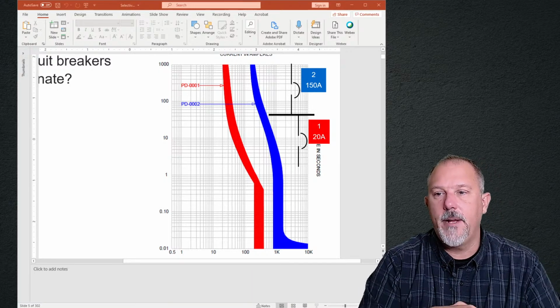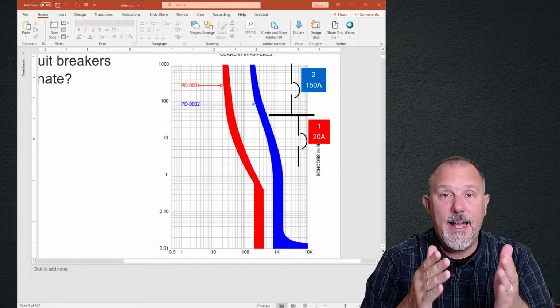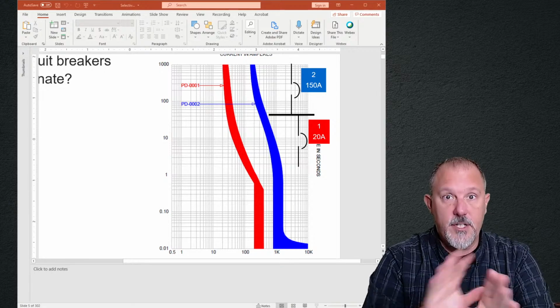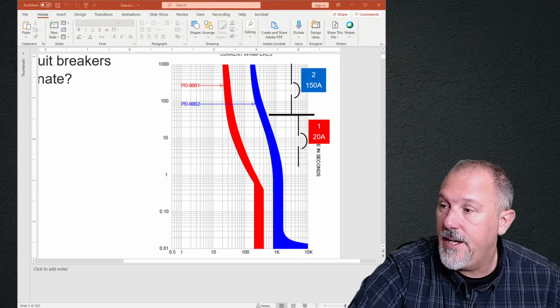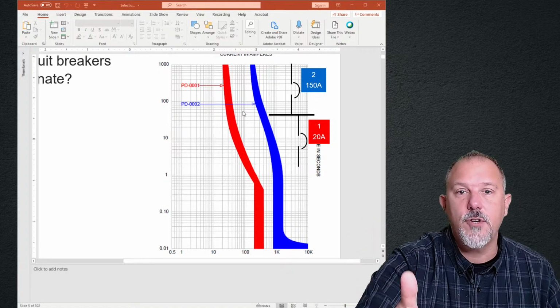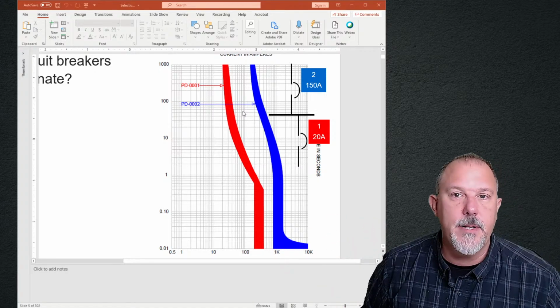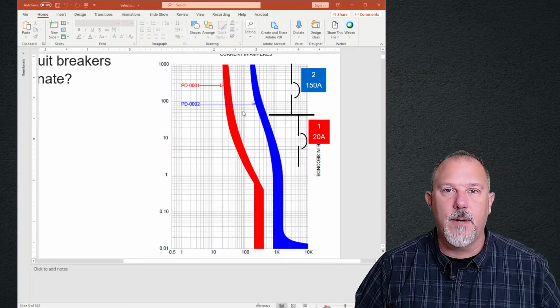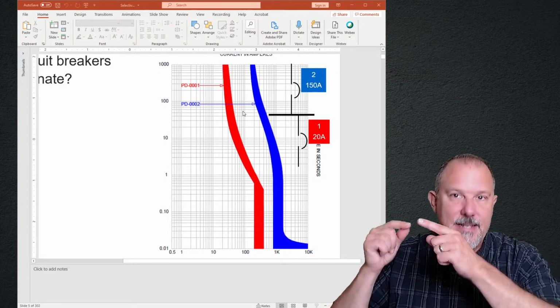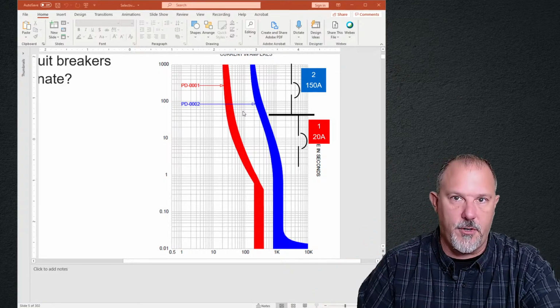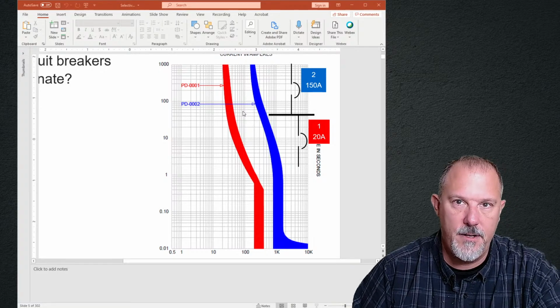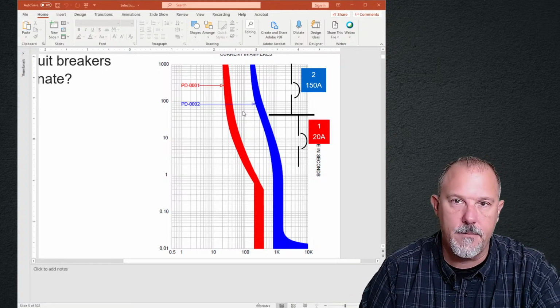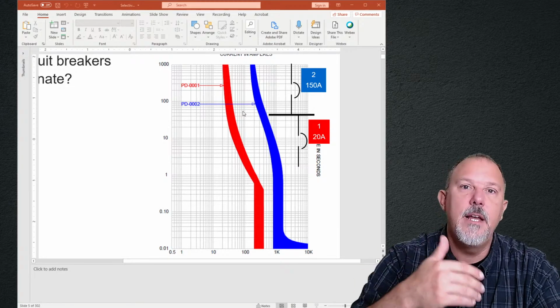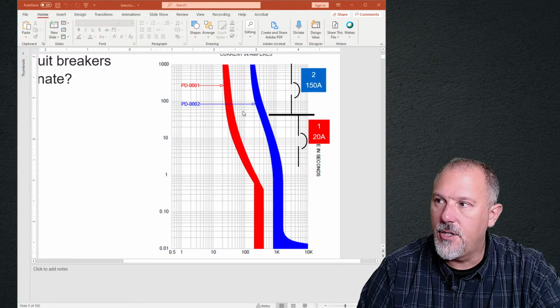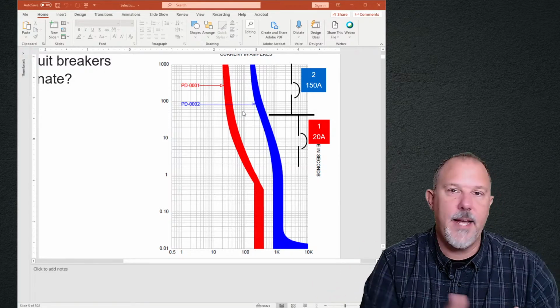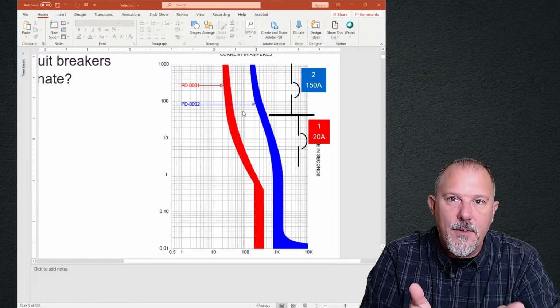Does the system have to be fully rated in lieu of series rated? Yes, David, they have to be fully rated. Now, let me just say this. If my fault current for this pair is 1,500 amps, if my fault current is less than 1,500 amps, would I be buying a series rated system? No, because everything is rated to interrupt. If you are looking at and buying a series rated system, it's because your bolted fault current values are high enough to exceed the interrupting ratings of that downstream breaker. And if they're high enough to exceed the interrupting rating of the downstream breaker, then the upstream breaker is going to open to help protect the downstream breaker at those values.